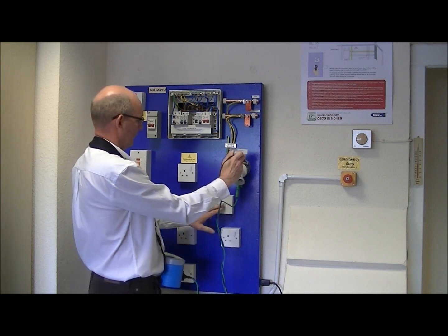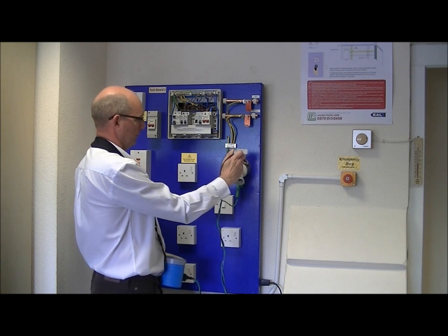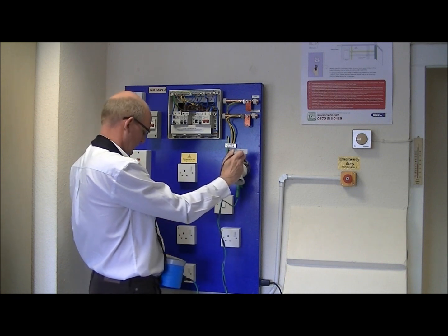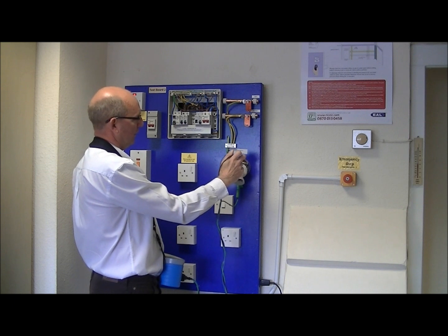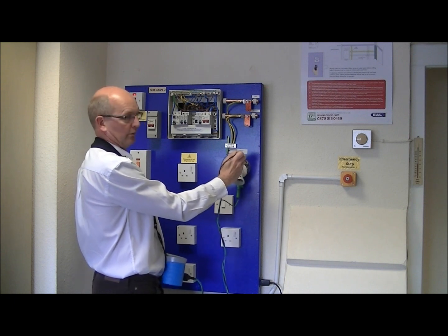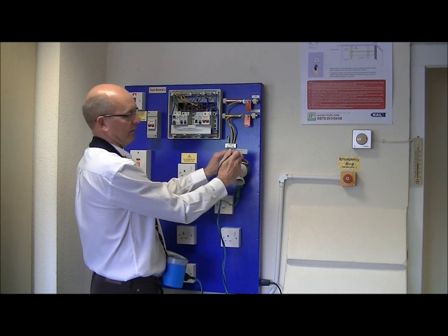It's a two-way lighting circuit, so we just need to put the switches in the opposite position to check to see if there's any difference with the different switch position. So we're running the test, and this time it's 0.85, so negligible difference. But anyway, the highest value is recorded on the schedule of test results. So that basically completes the test.